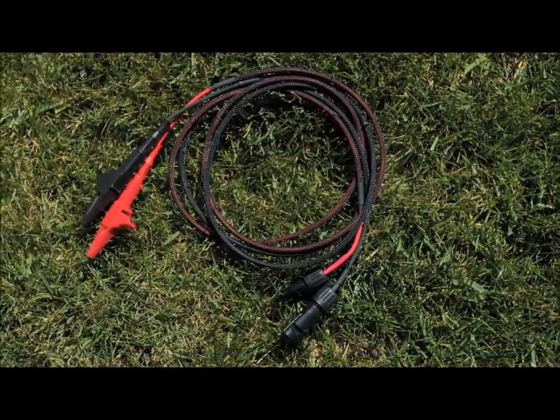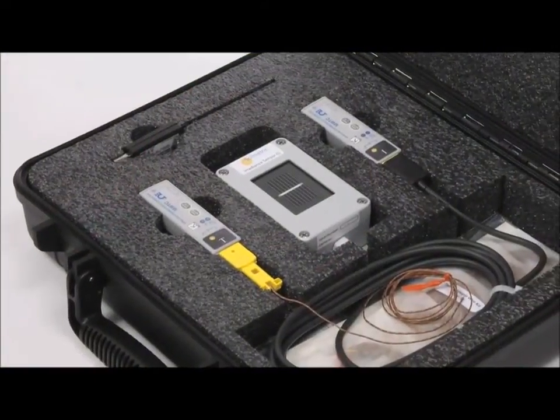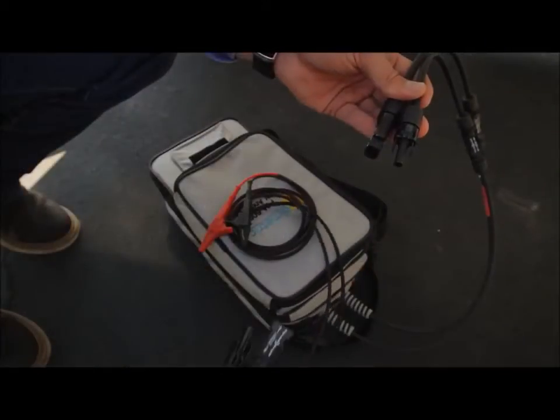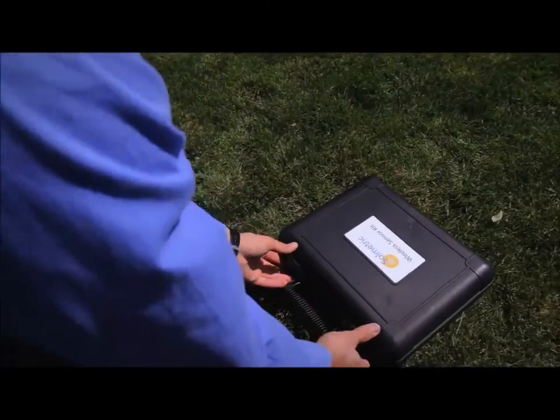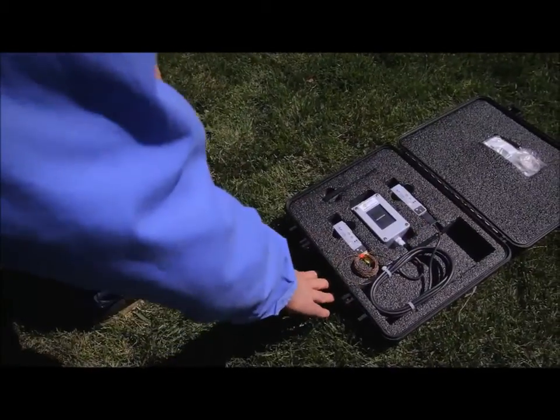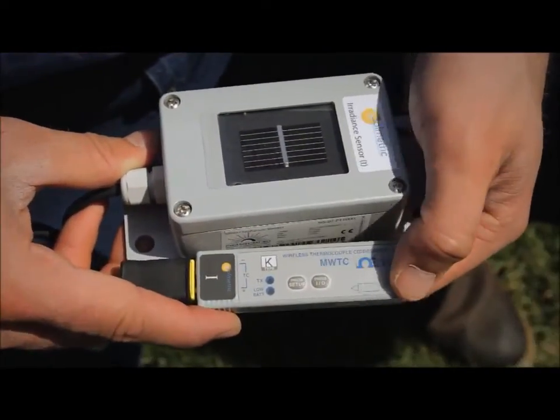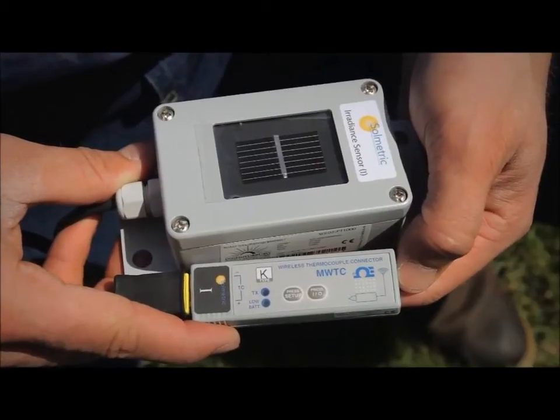Other optional accessories include PVA test leads and the wireless PVA sensor kit. The PVA test leads are 5 feet long and terminate in high current alligator clips. Irradiance and temperature are normally measured to ensure accurate model calculations. These values are constantly changing and irradiance in particular can change very rapidly.